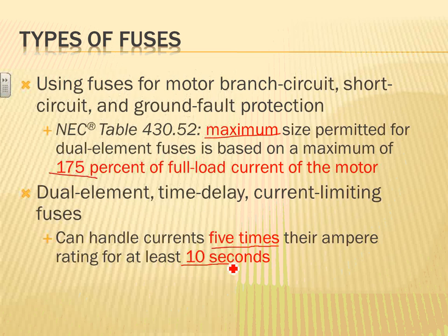So what would that be? That's your starting current on the motor. For 10 seconds, what happens after 10 seconds? If you go to 11 seconds, this will be seen as a ground fault or short circuit, and bam, it will sever and open the dual element time delay fuse. The fuse is rated for 5 times.